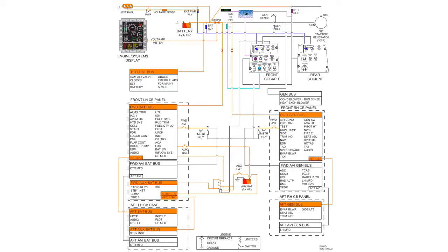to the starter, energizing it and starting the engine. As the PMU senses the engine is up and running, it will deactivate the starter relay, removing power from the starter. You can also put the starter switch in the manual mode to bypass the PMU. However, this will inhibit auto start protections. Once the engine is up and running, we can now signal the lineman to disconnect external power.